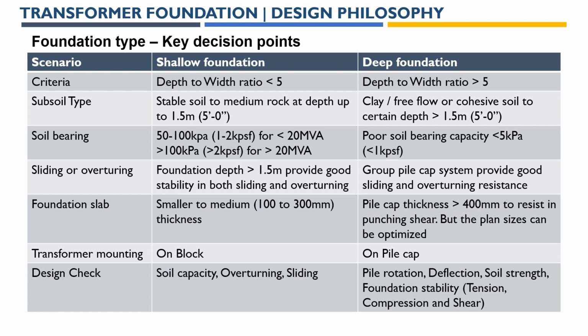Pile cap thickness generally needs to be greater than 400 mm or 450 mm. Even for oil containment slabs we need to go for 400 mm or 1.5 feet, to resist punching shear, because the pile will generate significant punching shear on the slab.